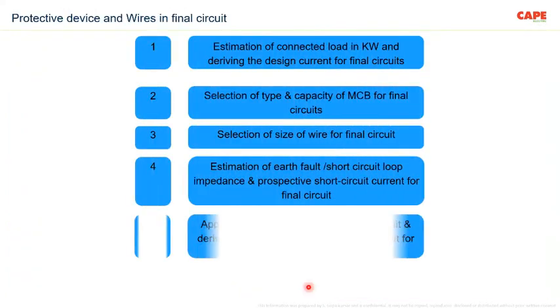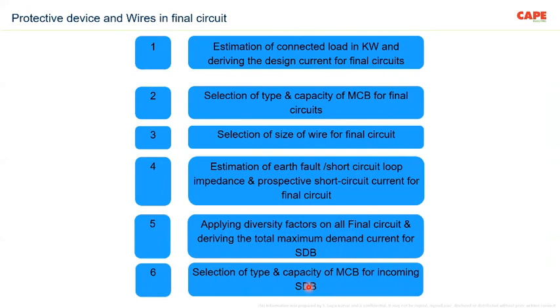Now, while selecting the MCB, the steps you are supposed to follow are, number one, estimation of the connected load in kilowatt. First you should find out what the current requirement is, also the starting current. Then selection of the type of the MCB, because the first one is the load requirement. Then we should select the protective device. Third, we should select the wire, including its length, voltage drop, condition of installation, the derating factors, and so on.